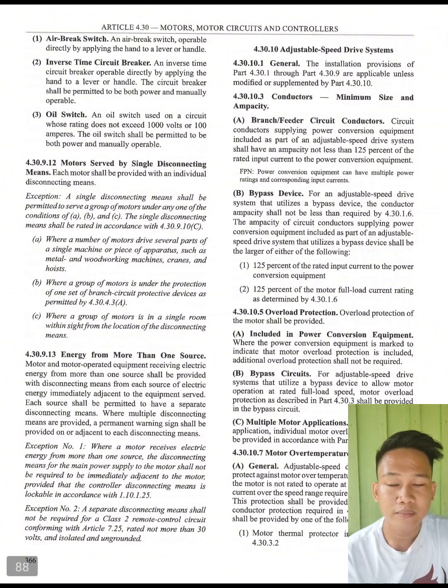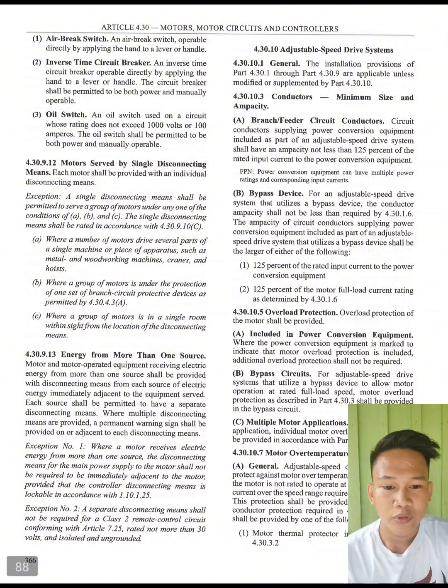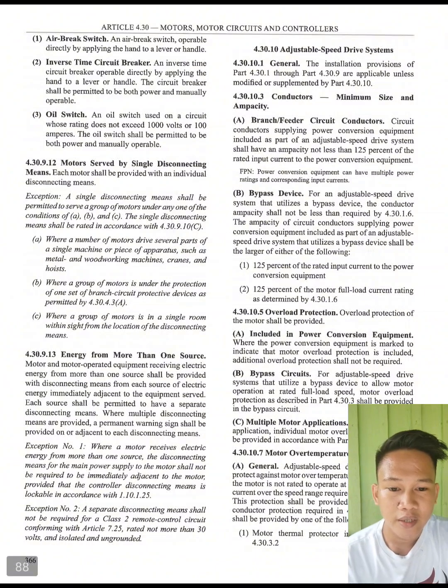So next you have 4.30.9.12, motors served by single disconnecting means. Each motor shall be provided with an individual disconnecting means. So, exemption. A single disconnecting means shall be permitted to serve a group of motors under any of the following conditions of A, B, and C.